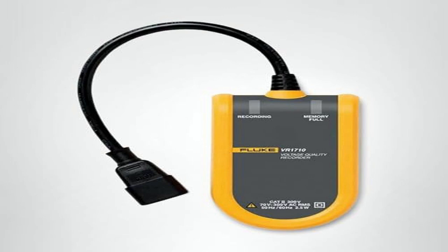Let's start with the kind of job the VR1710 is built for. It's aimed at anyone who needs to monitor power quality over a full workday or even longer without having to stare at the meter every 5 minutes. Think about a manufacturing floor that sees frequent motor starts, a data center where a subtle voltage sag could trigger a server reboot, or a commercial building where you suspect an intermittent flicker that's hard to catch on a standard multimeter. In those scenarios, you want a recorder that will sit on a wall outlet, capture every millisecond of voltage, current, frequency, and harmonic data, and then give you a clear visual summary that you can hand off to an engineer or a contractor.